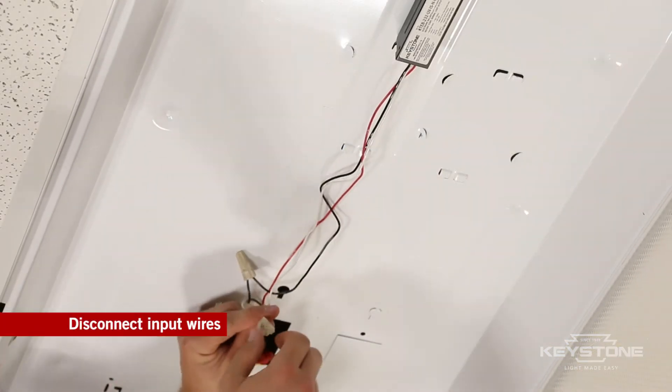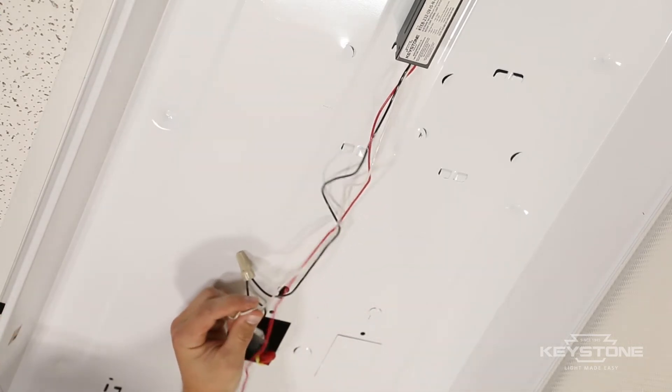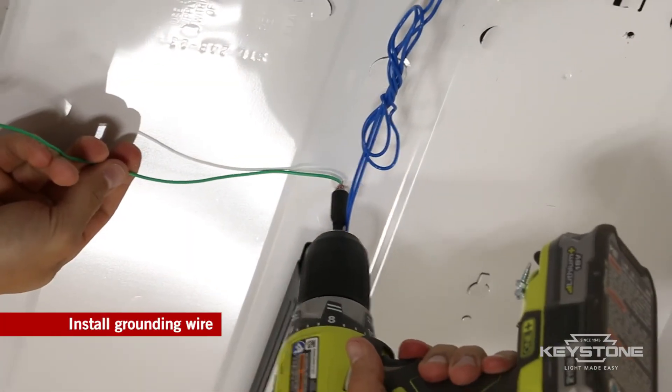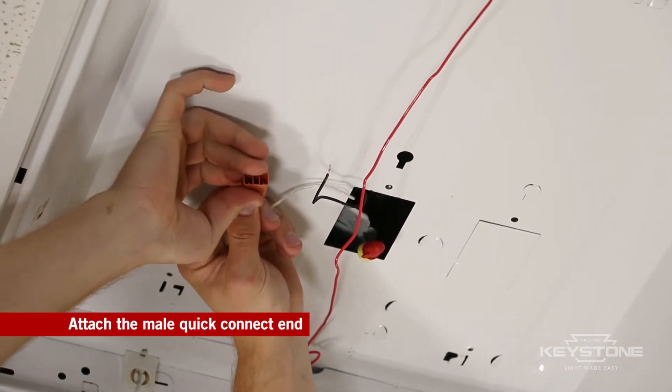Disconnect the input wires from the ballast by removing the wire nuts. Connect the green grounding wire on the FutureFit kit to the existing fixture.